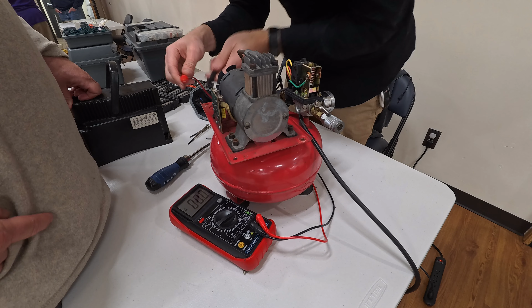We got a power strip to make it easier to turn the unit on and off instead of plugging it in each time. Once we got that set up, we started doing some more voltage checks on the board. Basically, the voltage on the board was 120 volts, which was good. But then we had to troubleshoot what was on the board, and you'll see me checking the different voltages at different spots just to make sure we were getting 120 volts AC.